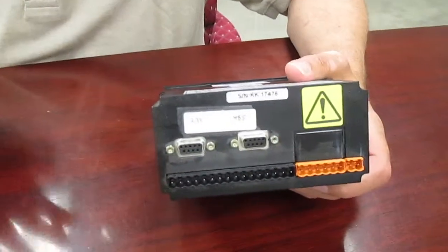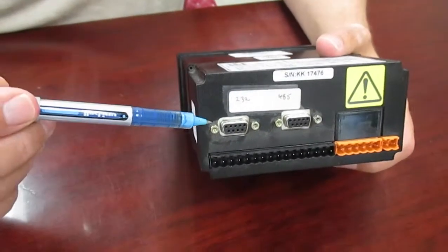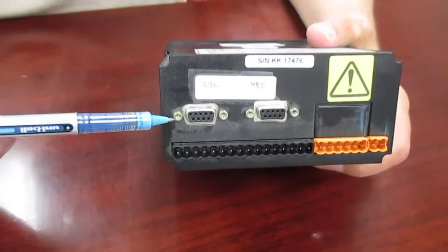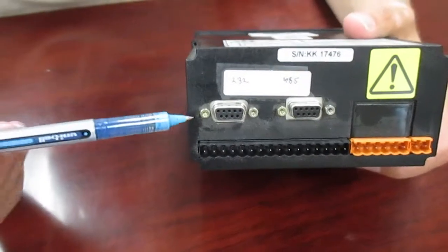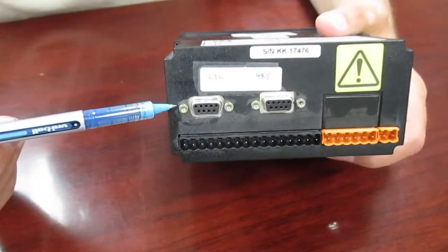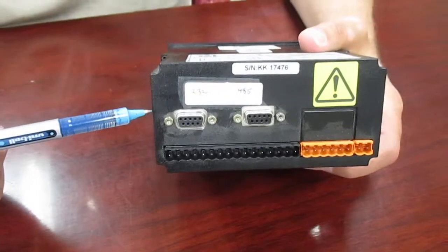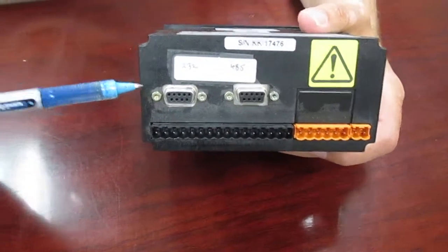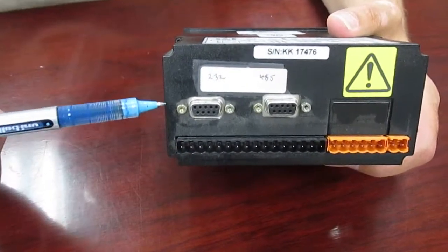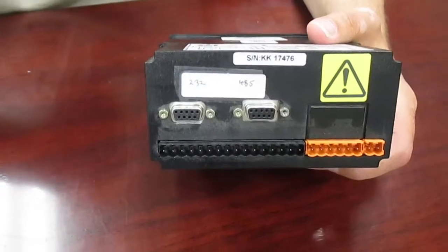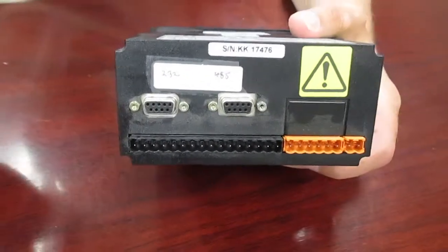The standard communication port that KEP comes standard on all flow computers in these two families is the RS-232 serial port. This is always found facing the rear of the unit all the way to the left-hand corner. This communication port is used for using the free setup software that comes with every unit to actually set the flow computers up. It can be used for connecting to a printer, and also can be used with the optional polling software that allows you to do remote metering or downloading of data logging.